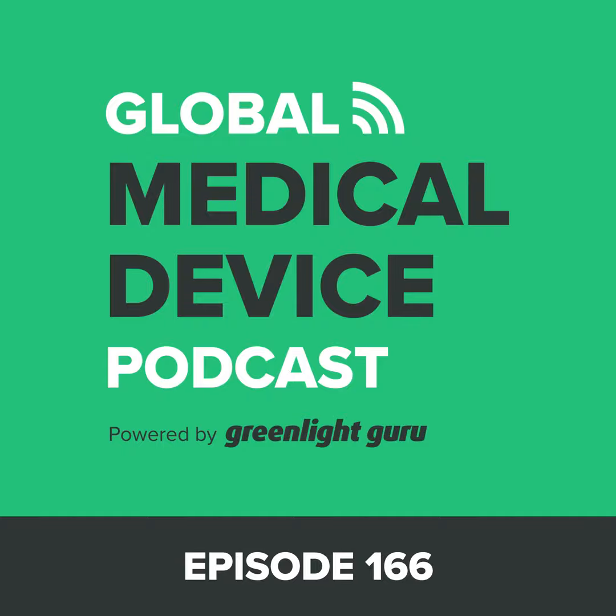The other two guidances are finalized guidances. And keep in mind, John, as we've talked about before, there's really no such thing as a final guidance, but that's what FDA calls it. The first one is technical considerations for non-clinical assessment of medical devices containing nitinol. That originally came out as a draft about a year and a half ago, and now FDA has just finalized it.